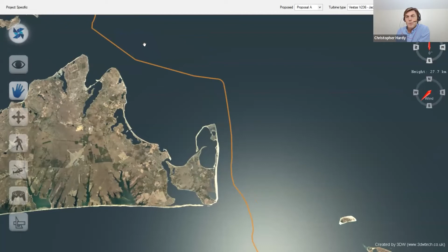Expected cable distance to Falmouth is between 52 to 87 miles. There will be up to 3 submarine cables and up to 1 telecommunication cable within this corridor. The cable corridor will be between 2,600 and 3,300 feet, or about half a mile, to enable maneuverability during installation. The proposed cable depth is 6 feet below the level seabed, with each cable separated by about 328 feet, varying based on bathymetry.